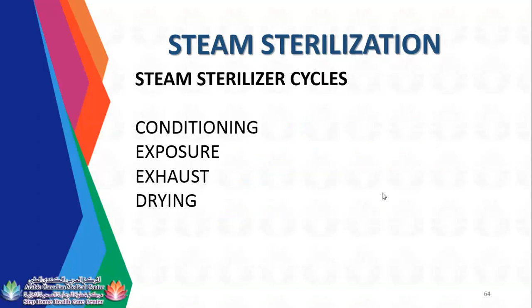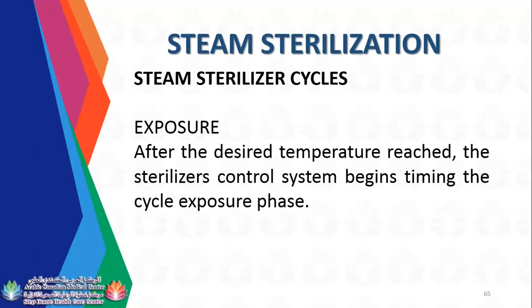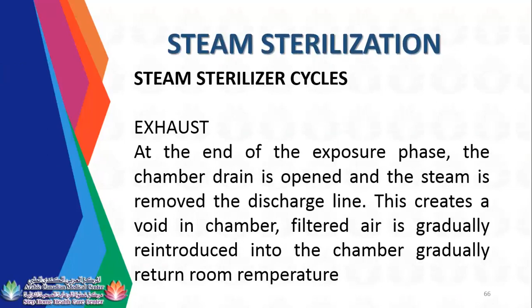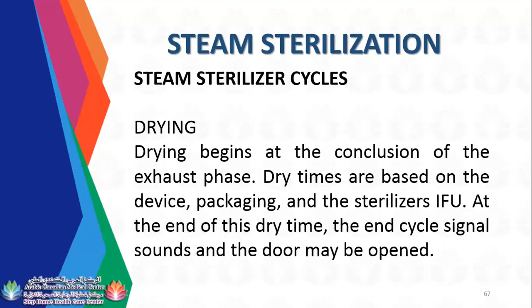Actually, I already discussed this in the first or second topic or introduction, I think. Steam sterilizer cycles, exposure: after the desired temperature is reached, the sterilizer control system begins timing the cycle exposure. Exhaust: at the end of the exposure phase, the chamber drain is open and the steam is removed through the discharge line. This creates a vacuum in the chamber. Filtered air is gradually reintroduced into the chamber and gradually returns to room temperature. So drying begins at the conclusion of the exhaust phase. Dry times are based on the device packaging and the sterilizer's IFU.